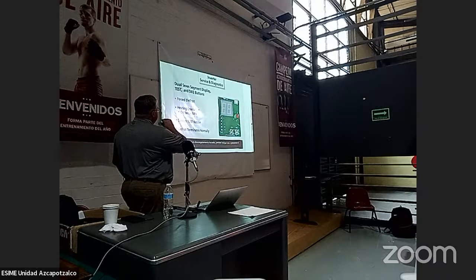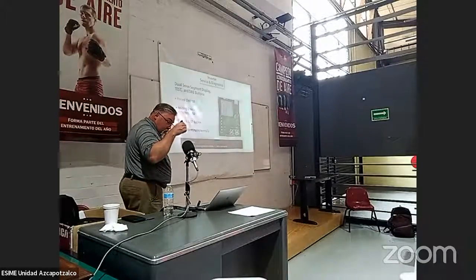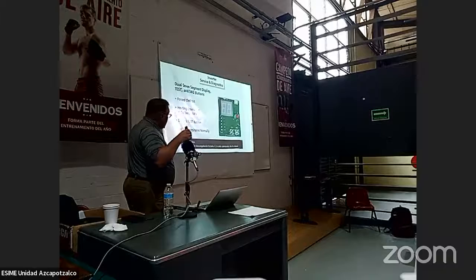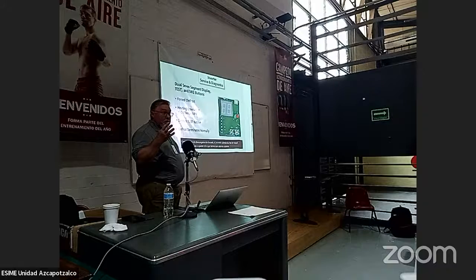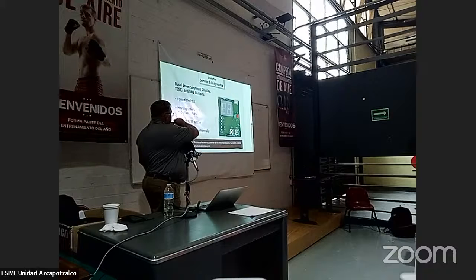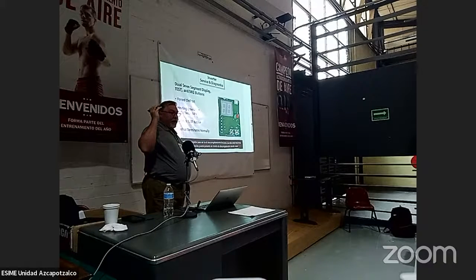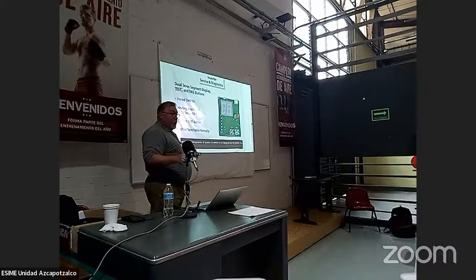So you can do a forced defrost. You're going to press the test button. You go into forced defrost, you have your heat. The thing you have to know is, if you want to test defrost, to see if defrost works when you're doing a new installation, put it in the defrost mode from here, but you need to make sure that the outside air temperature is below 50 degrees. If it's not below 50 degrees, it won't go into defrost. So it has to be there.